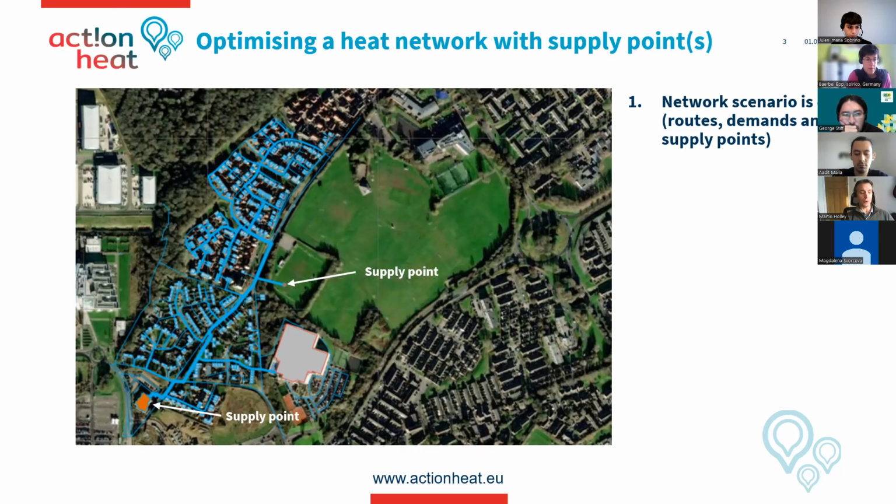ask Thermos to optimize. So you have to set this up by importing a map, basically, and Thermos will then estimate the energy demands of all the buildings on that map, and you then categorize all the buildings according to whether they should be optional in the problem, in the scenario, whether they should be required, so the model will be forced to include them in the problem, or whether they'll be forbidden. You know, they shouldn't be included in the problem.